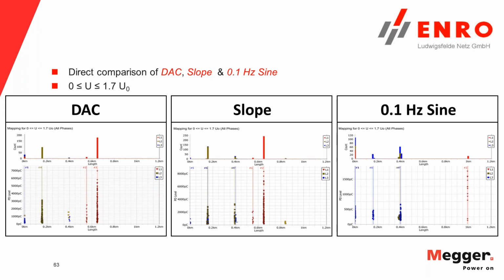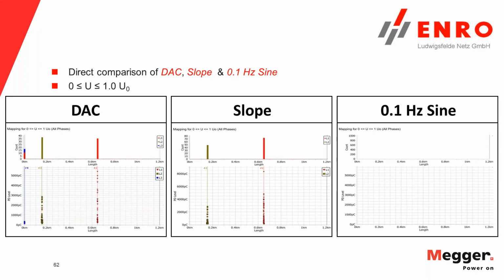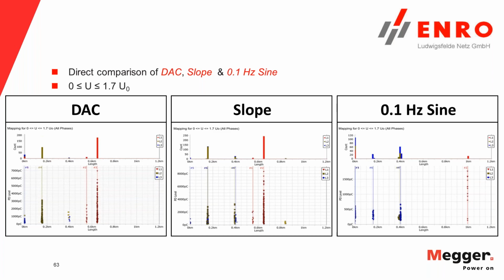And if you go on, then it goes into the thousands. And then down there, you see the cloud patterns that form. Look at the magnitude. Sinusoidal, 250, 500 in that area. And the other two waveforms are in the thousands, so alarming. And again, at operating voltage, the condition was already present, and sinusoidal just measures it now.